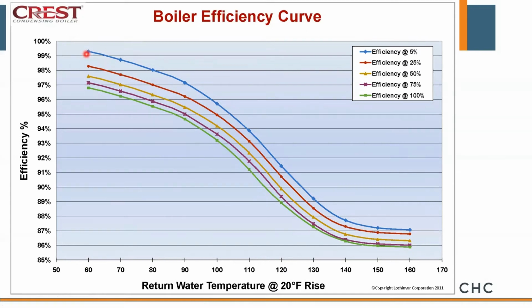Now remember at the start of this, we talked about a boiler is nothing more than a fancy heat exchanger. If we take this boiler and we drive it to high fire, okay, or 100% firing rate, you'll notice that our efficiency drops a little bit. It goes from 99% down to under 97%. And why is that? Why are we losing 2%? Simply because a lot of that heat isn't getting absorbed by our heat exchanger. We might lose some of that heat up the vent pipe, okay? We might lose some of it through our jacket losses, and we might also lose it through condensate lines. So our boiler's always more efficient at low fire versus high fire. We have more surface area absorbing minimum heat than we do at high fire, okay? So you'll notice as we start to move out here, as our return water temperature increases, our efficiency gets worse.